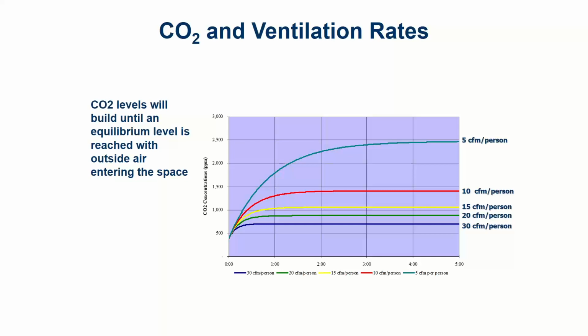So if I was at approximately that 17 CFM per person range, somewhere between the blue or the green and yellow line, it would take about half an hour or so to stabilize the room. That doesn't mean I wait a half an hour to start opening the ventilation damper. I will start opening it right away. As soon as people come into the conference room, I'll start ventilating. As they leave, I'll slow down the ventilation rate.